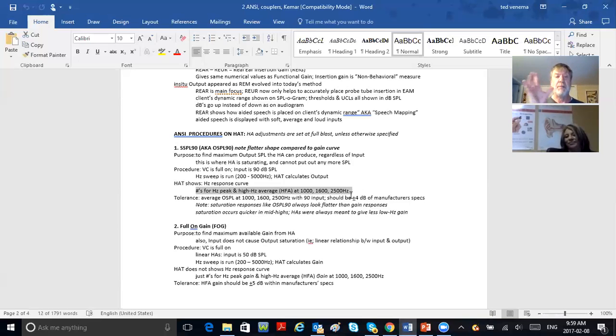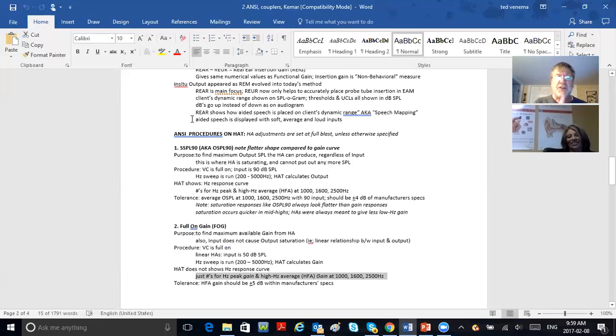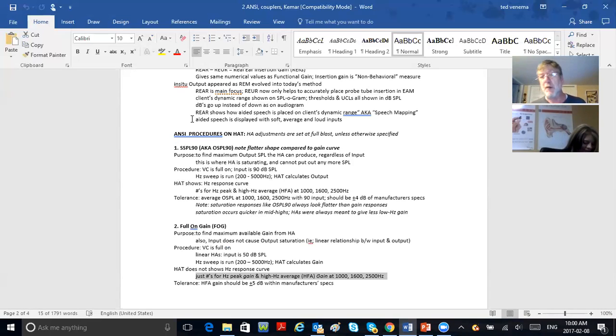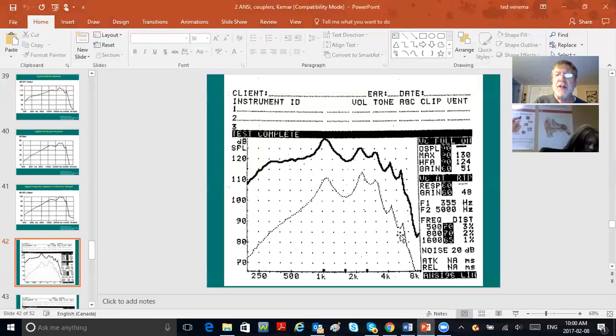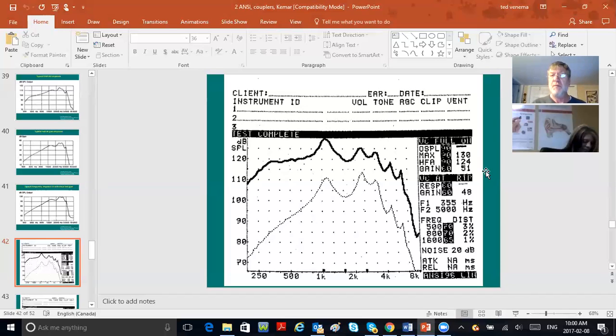Full-on gain does not—repeat, not—show any frequency response curve; it just gives you numbers. The tolerance should be within 5 dB of manufacturer specs. Some equipment shows peak gain, some shows high frequency average gain, some shows both. In this equipment, what's shown is just a single gain number for a 50 dB input—in this case, 51 dB.